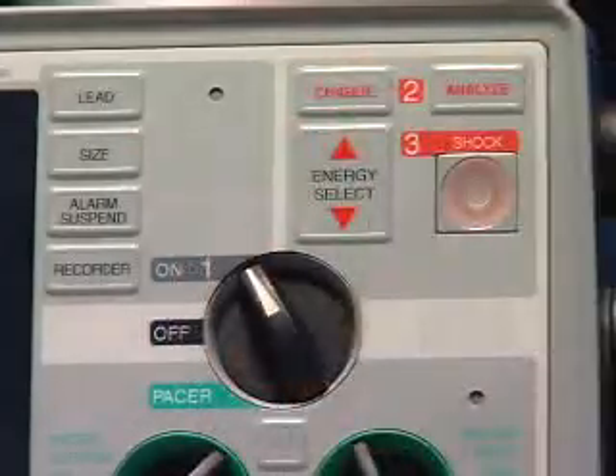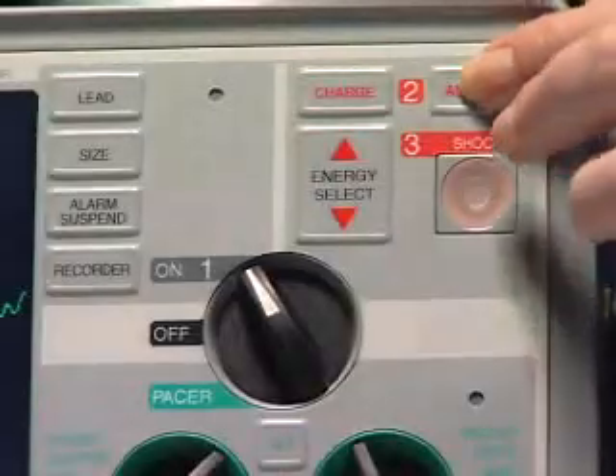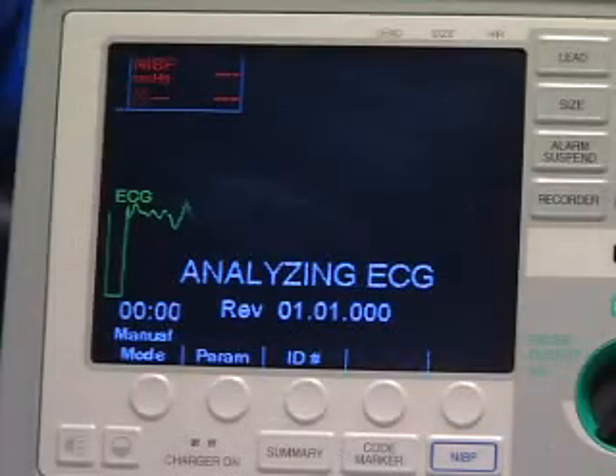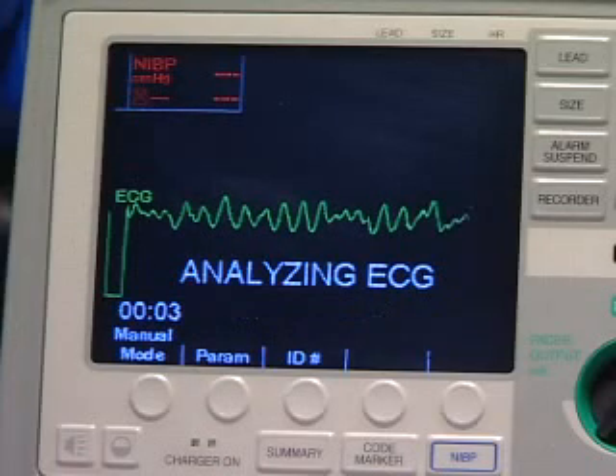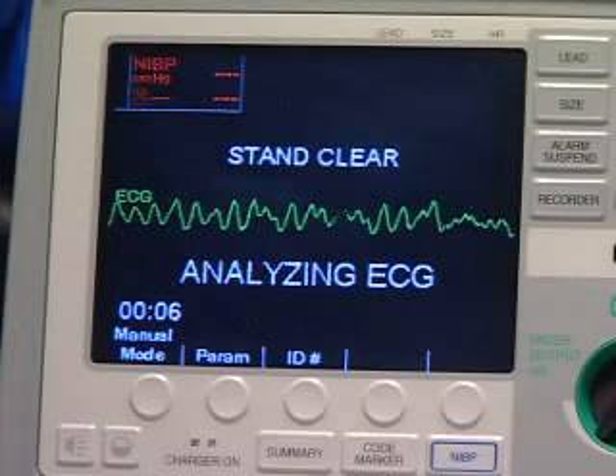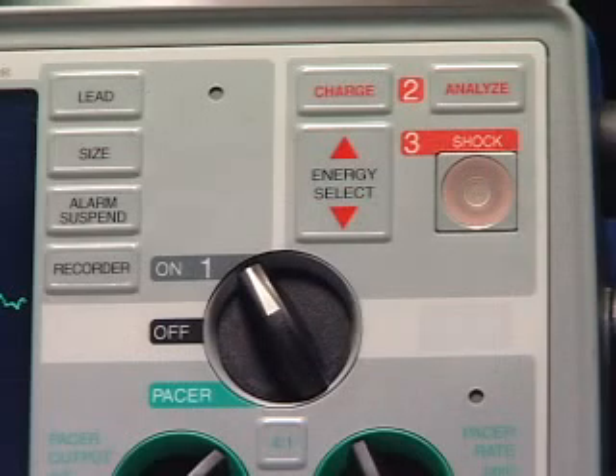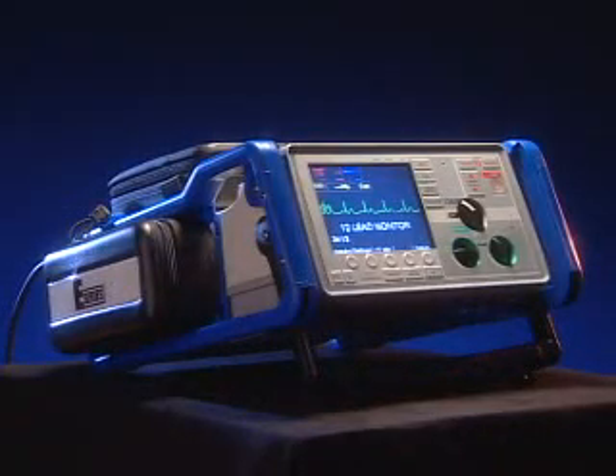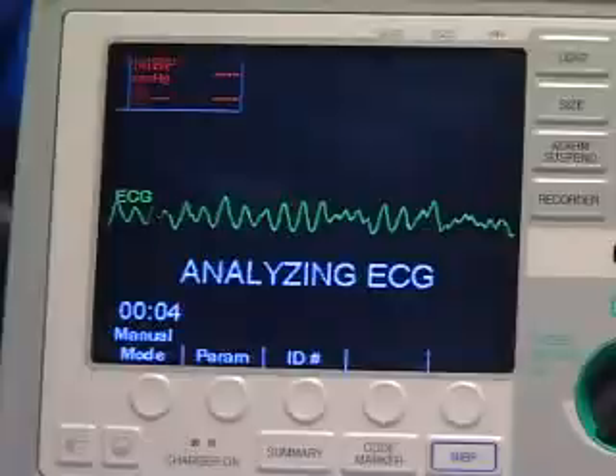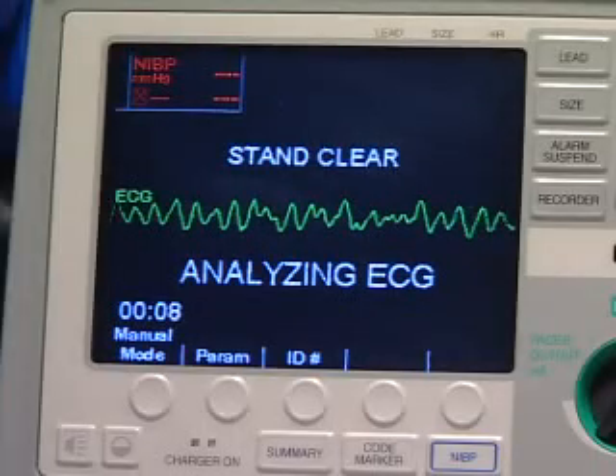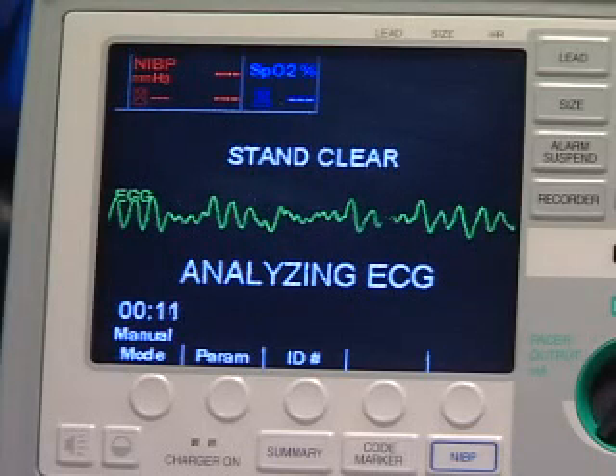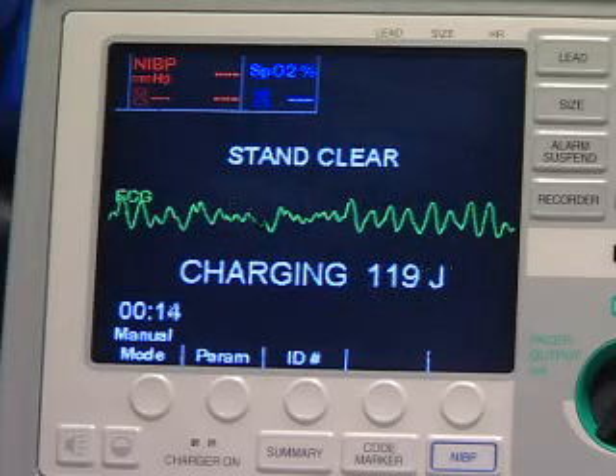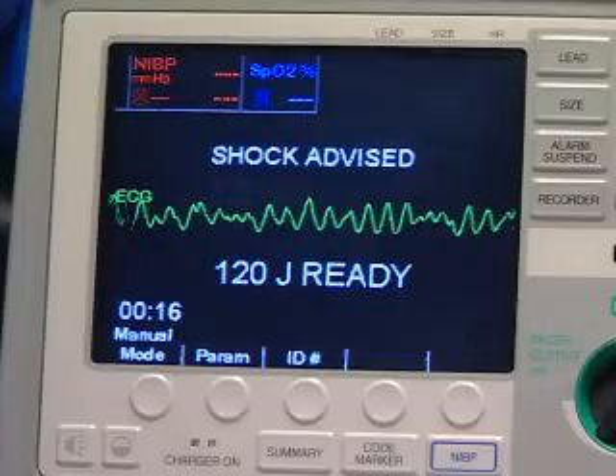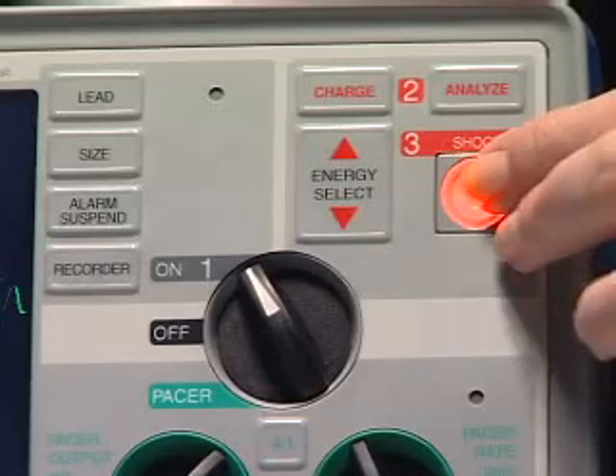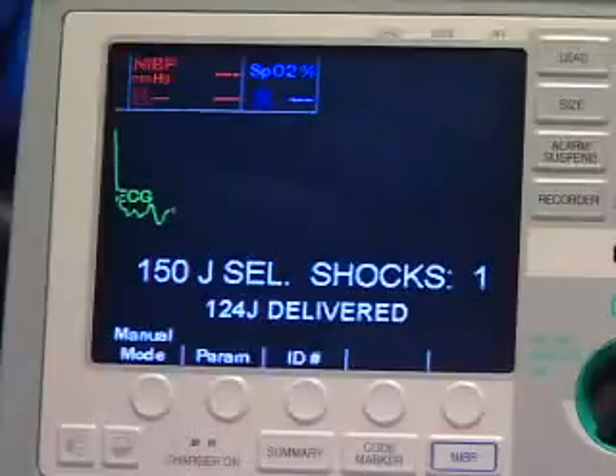The second is in the user-activated mode, initiated by pressing the Analyze button. The user-activated analysis can only be done when the multifunction electrode pads are connected and firmly attached to the patient, and when the selector switch is turned to on. The E-Series AED with manual override option can be configured to automatically analyze on power up. Stand clear. It will then automatically charge if a shockable rhythm is detected. Press shock. You will need to press the shock button to deliver the shock to the patient.